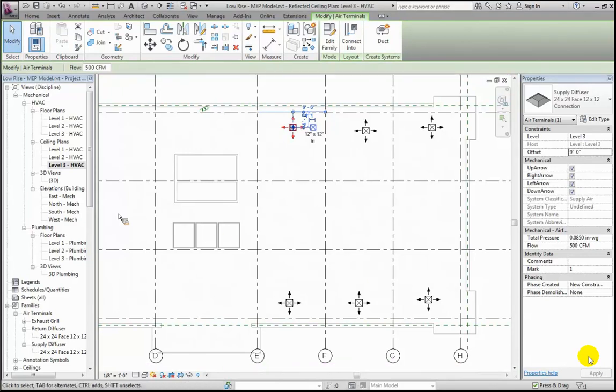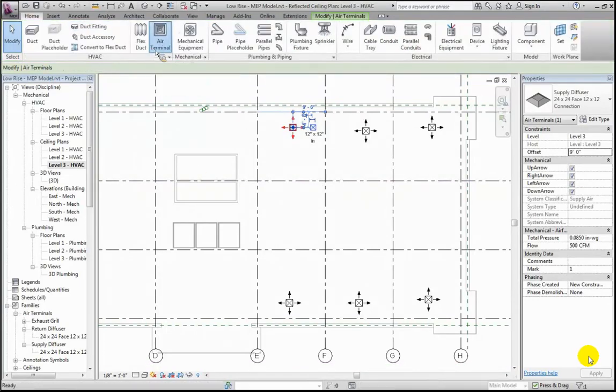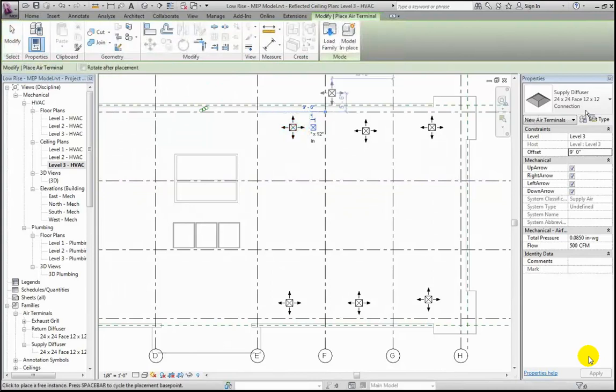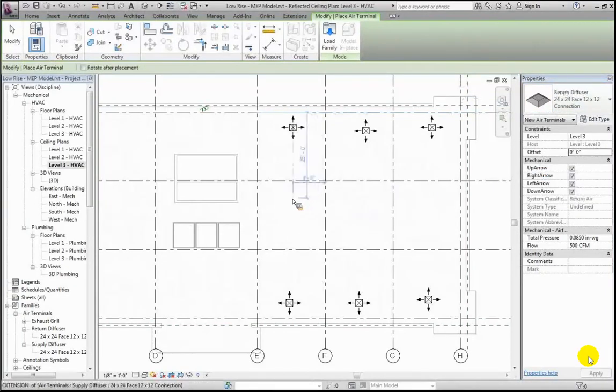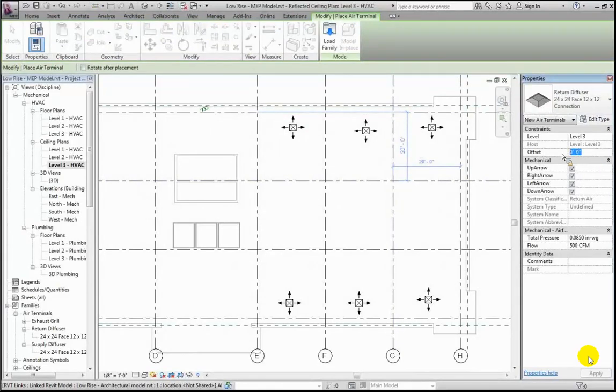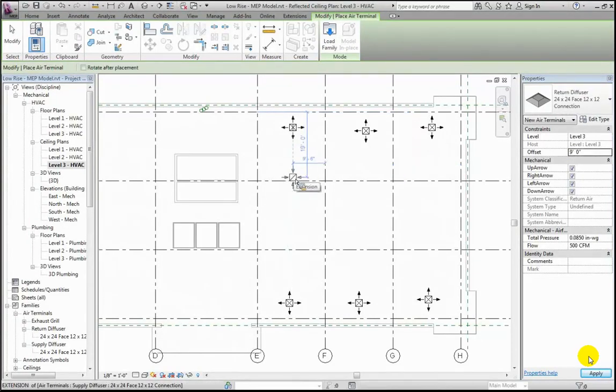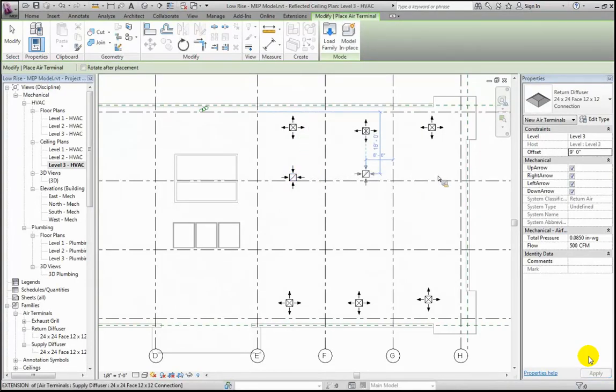Similarly, I'm going to put in some return terminals to pull that air back to the air handler, which I envision being somewhere over in the center of the building. I'll go back to the Home tab, choose air terminals, and this time select return instead of supply, placing them at about nine to ten feet off the ground. Notice the arrows actually indicate whether you're supplying or returning — a common strategy is to pull air toward the middle of the building and return it that way.